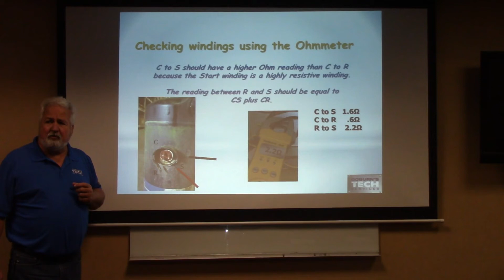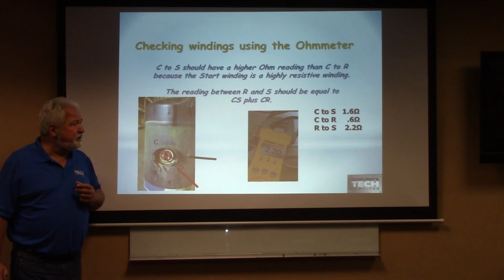So if I go from run to start, it should be the combination of both of those. Is that right? Good. So what you're expecting to see is 1.6 plus 0.6 is 2.2 ohms is what I should be seeing right there. So let's look at that. If I saw that I had 1.6 on my start, 0.6 on my run, I should see the combination of both of those resistances between the run and the start. Everybody cool? Good, good, good.